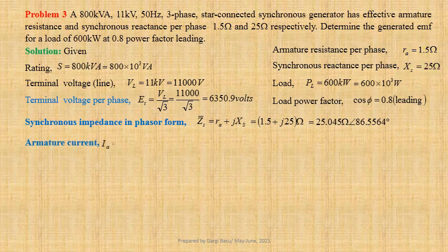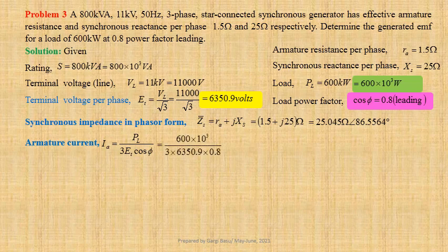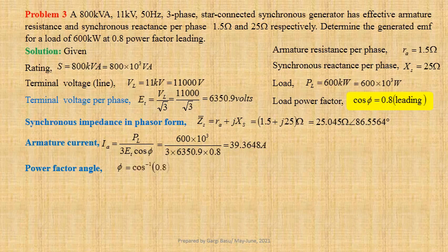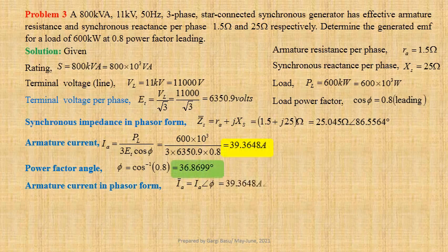Armature current IA equals PL divided by 3 times ET into cos phi. Using values we get 600 into 10 to the power 3 divided by 3 into 6350.9 into 0.8. That gives us 39.3648 ampere. Power factor angle phi equals cos inverse 0.8, that is equal to 36.8699 degree. Armature current may be written in phasor form as IA equals IA at an angle phi, that is equal to 39.3648 ampere at an angle 36.8699 degree.